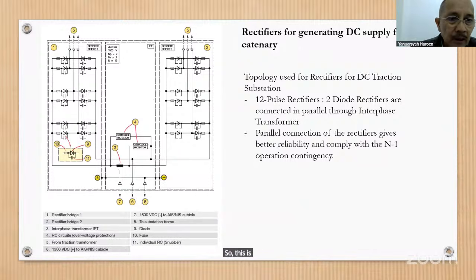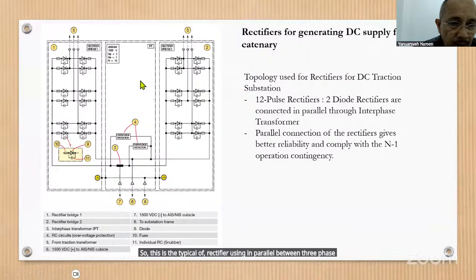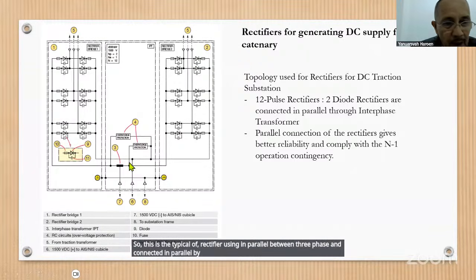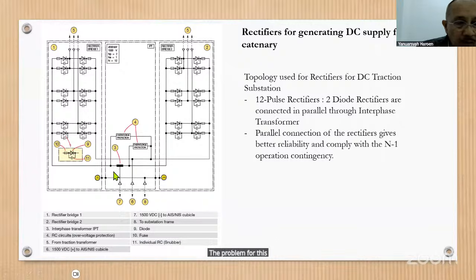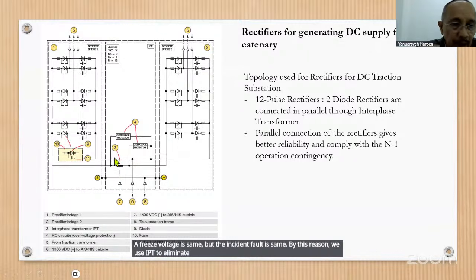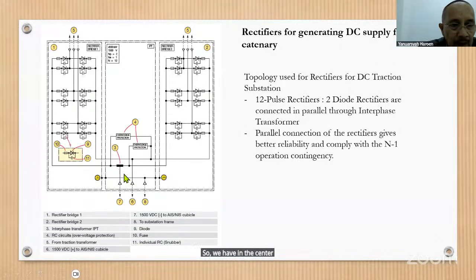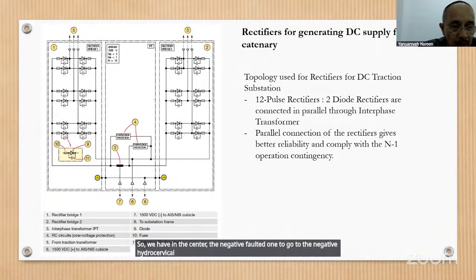This is the typical rectifier setup using parallel connection between three-phase transformers connected in parallel via an interphase transformer (IPT). The problem with this kind of connection is that while the average voltage is the same, the instantaneous voltage is not, so we use the IPT to eliminate this difference. In the center, the negative voltage goes to the negative feeder cubicle or the rail, so the rail remains floating.